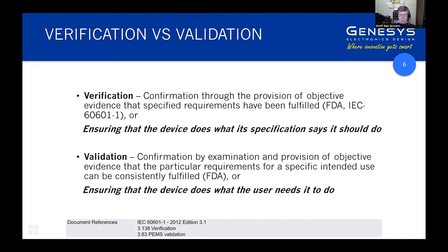And that also can follow through to a device, for example, that's a diagnostic tool. You may be able to do trialing on animals. And I do remember a situation with a cervical cancer tool of doing tests on squid skin and on pigs' cervixes, of all things, to show that the device's basic function can do some of the testing discrimination that the actual device will need. So it's a long-winded answer to say, yes, at the earliest opportunity, but be really careful not to confuse clinical trials with preclinical evaluations or informal investigations.